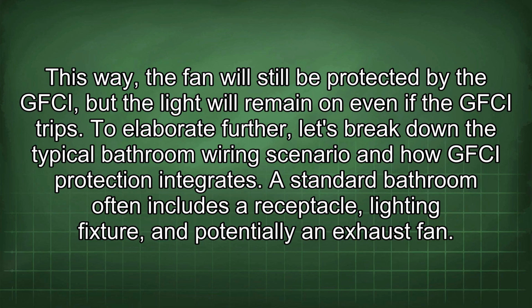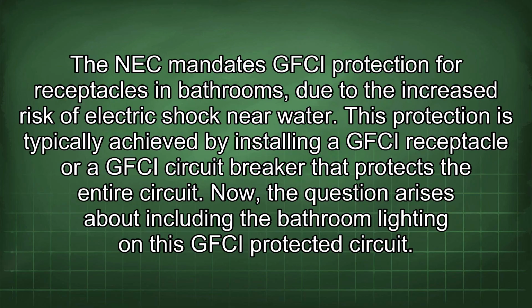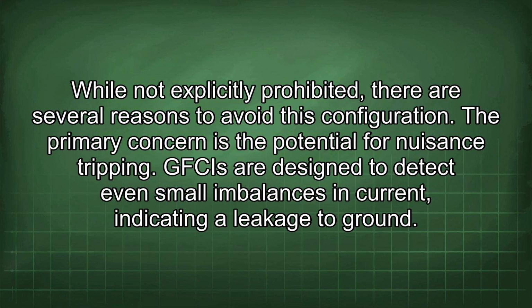A standard bathroom often includes a receptacle, lighting fixture, and potentially an exhaust fan. The NEC mandates GFCI protection for receptacles in bathrooms due to the increased risk of electric shock near water. This protection is typically achieved by installing a GFCI receptacle or GFCI circuit breaker that protects the entire circuit. Now, the question arises about including the bathroom lighting on this GFCI protected circuit. While not explicitly prohibited, there are several reasons to avoid this configuration.